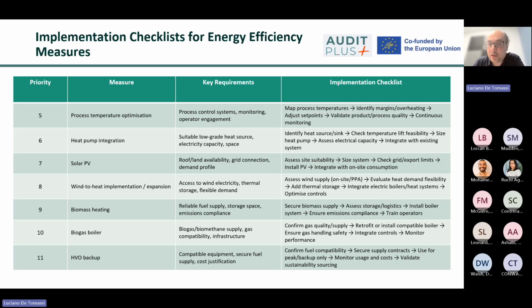Some comments about instrumentation, controls, and monitoring. Effective monitoring and control are essential to achieve and sustain expected energy savings. Key checks include the installation of appropriate energy meters and submeters, calibration of temperature, pressure, flow, and energy measurement devices, verification of communication systems and data acquisition, integration with SCADA or building management systems, development of energy performance dashboards and reporting tools, alarms and fault management configuration. Particular attention should be given to monitoring systems supporting electricity waste reduction initiatives, temperature controls associated with hot water temperature optimization and process temperature optimization, performance monitoring for heat pumps, waste heat recovery systems, and renewable energy assets.